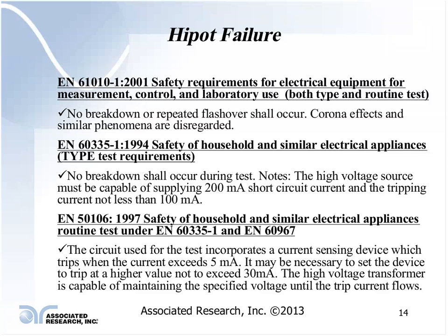They have multiple shutdown circuits for high and low currents, for arc detection, for GFI circuit protection. So there are much safer testers being designed and used today than there were 10, 15 years ago. You might want to take a look at some of the newer Hipots from that standpoint.